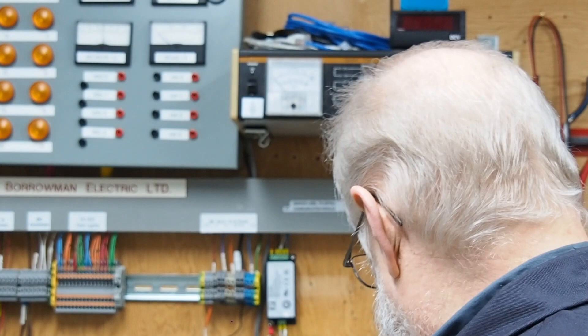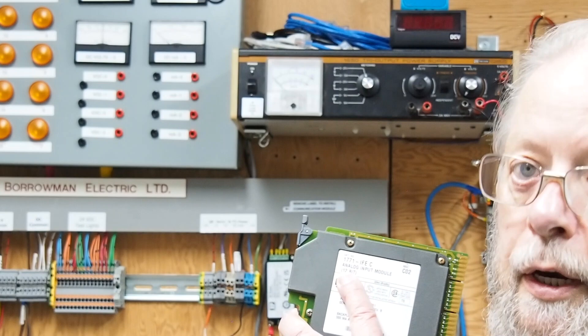You put a value, and this is all BCD or two's complement, and you put a value into the output card, that same value, plus or minus one or two percent, should be able to be read in the input card. The other thing to notice on these is these are 12-bit. They're not the 16 or 32-bit of today's cards, they're 12-bit. And industry ran on that for many years.